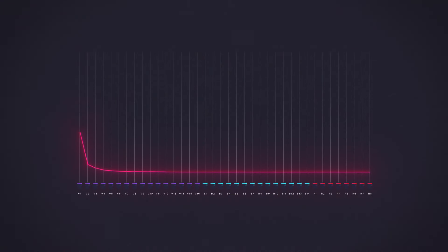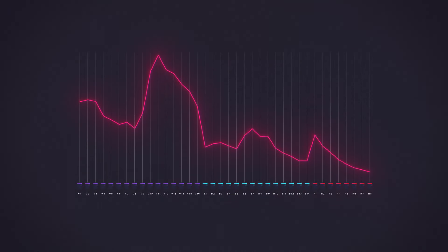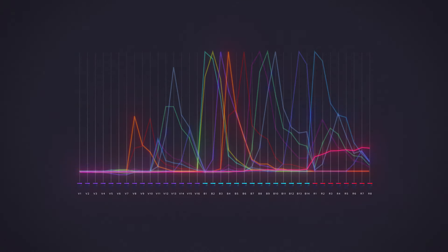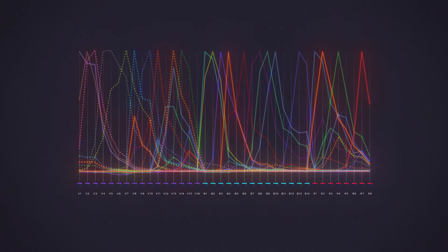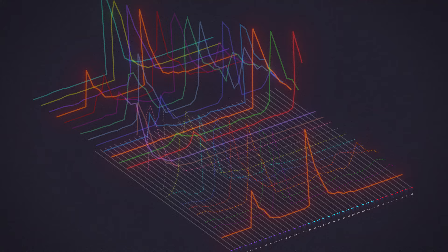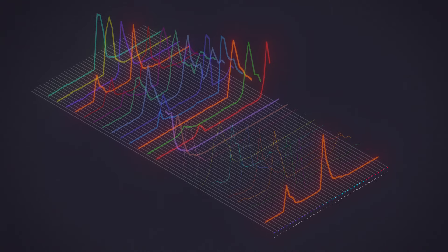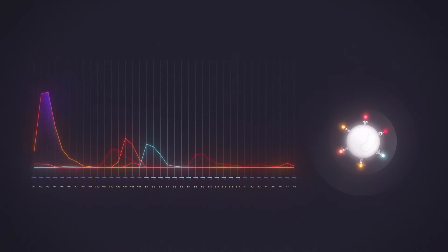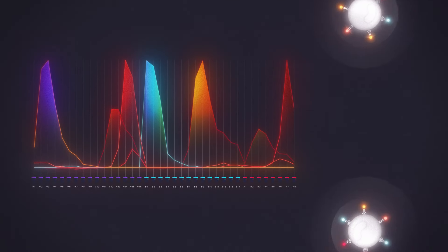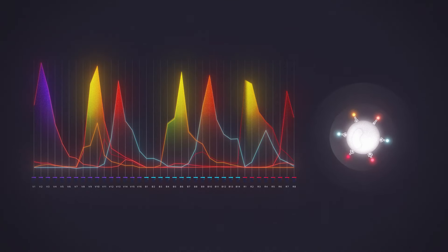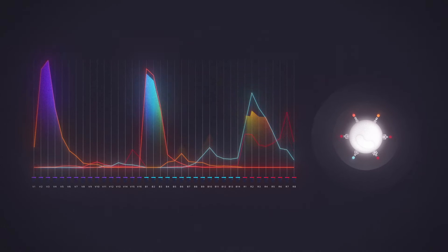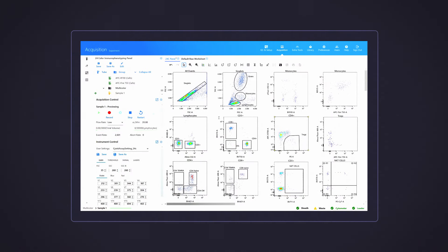For each fluorochrome present in a sample, a full-spectrum signature is generated by measuring how much light it emits across all the APDs. After each fluorochrome's full-spectrum signature has been defined, the experiment is unmixed so that all the different signatures in your multicolor sample are identifiable in real time.